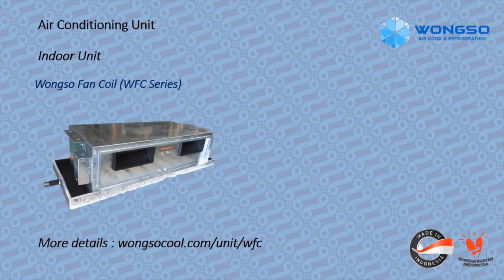Wongso Fan Coil Unit atau WFC series. Fan Coil Unit ini memiliki cooling capacity standar mulai dari 9.000 hingga 60.000 BTU per hour. Fan coil unit ini bisa digunakan untuk aplikasi direct expansion dan juga chilled water application. Blower dan motor yang digunakan adalah jenis direct drive centrifugal fan dengan 3 tingkat kecepatan, yaitu low, medium, dan high speed.